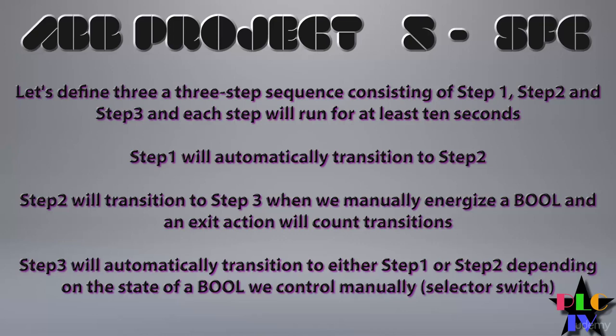Once we're in step two, we want to stay there for at least ten seconds, but we don't want to transition to step three until we manually close a bool. So we're going to have a bool, which is going to represent maybe a switch or a button or something like that. And until we make that true, we're not going to go into step three.